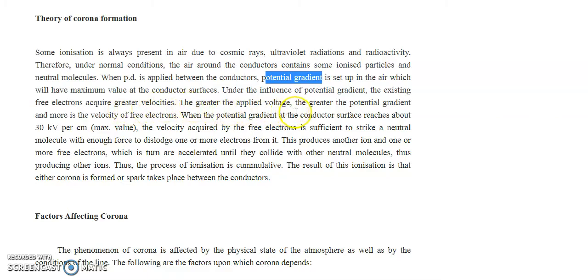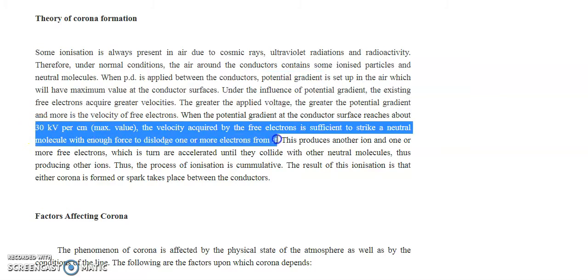The greater the applied voltage, the greater the potential gradient, and the more the velocity of free electrons. So you need to understand here, when you increase the applied voltage, your potential gradient will increase, and thereby your free electrons' velocity will increase. That's why we are saying that your corona is also increasing, right? When the potential gradient at the conductor surface reaches about 30 kilovolt per centimeter, you consider this as a maximum value. The velocity acquired by the free electron is sufficient to strike a neutral molecule with enough force to dislodge one or more electrons from it. So this is the marginal voltage required to discharge one or more electrons from it.